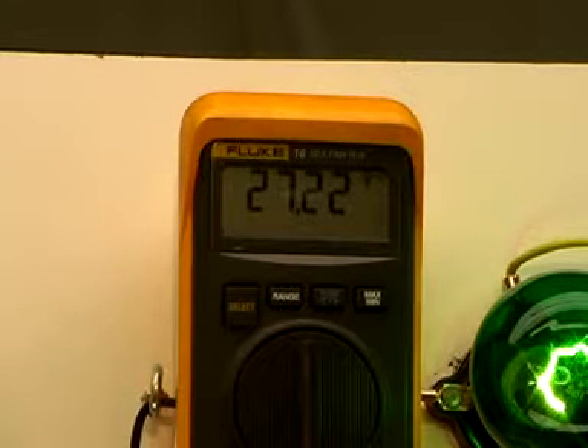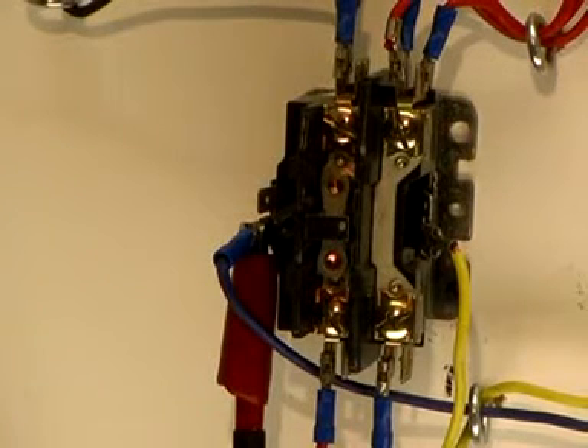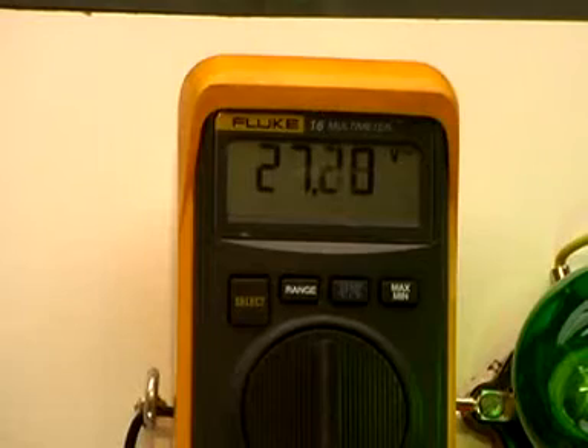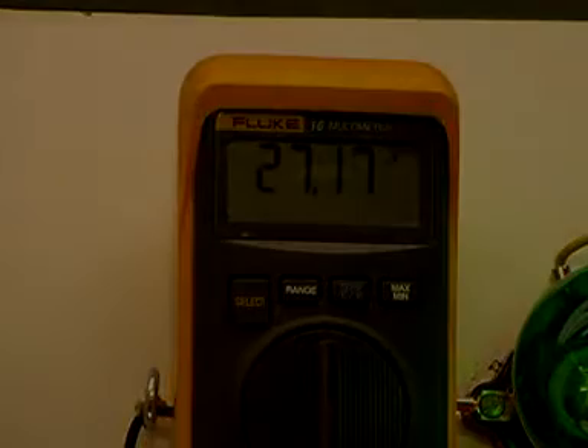Let's get back down there and read on the back side of the contactor coil and see what we get. So moving the probe over to the back side of the contactor coil, if in fact we read 0 voltage here, then we can say, yeah, there's something wrong with the contactor coil, it's opened up. But as we're going to see, the meter says that we read 27 volts again. So obviously we've got a problem somewhere else.